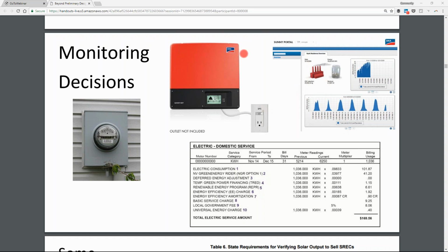Now, generally, these monitors inside the inverters are 95 to 96% accurate, and the utility will say that their meters are 99% accurate, 99.5% accurate. Some inverter companies will sell an upgraded monitoring system, which they call revenue grade monitoring or utility grade monitoring, to improve that accuracy just a little bit with, I guess, more expensive monitoring current transducers.